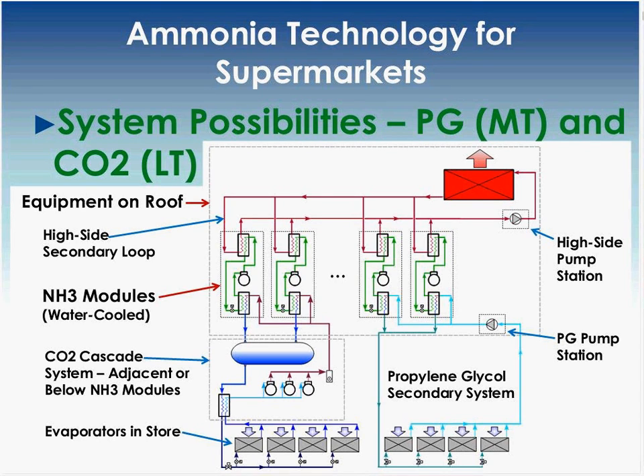This is a propylene glycol system for medium temperature and carbon dioxide for the low temperature type system. The line I'm pointing to would be the portion of the system located on the roof. This line is the carbon dioxide skid, which could be located on the roof or within the building. And these would be located throughout the various parts of the store.